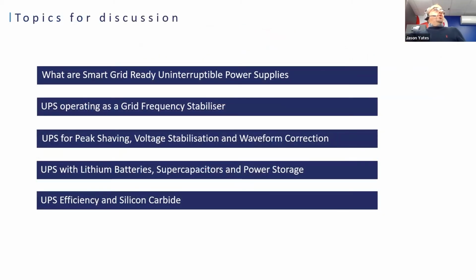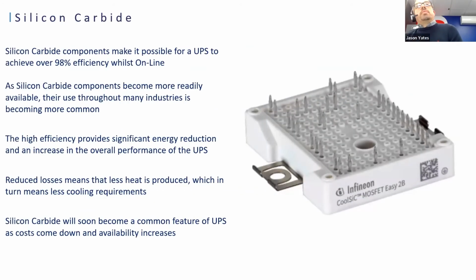So where are we going with UPS systems? Well, to finalize, the main thing about UPS is efficiency. We want to have UPS systems which are as efficient as possible. Efficiency obviously plays a key role in UPS, and the biggest change to the marketplace that we're seeing coming through at the moment is that silicon carbide components now make it possible for UPS to achieve over 98% efficiency whilst in online operation.